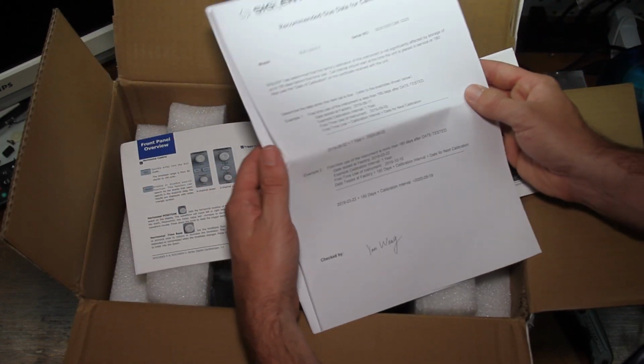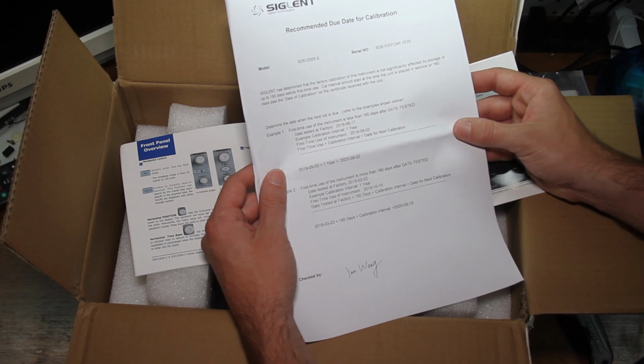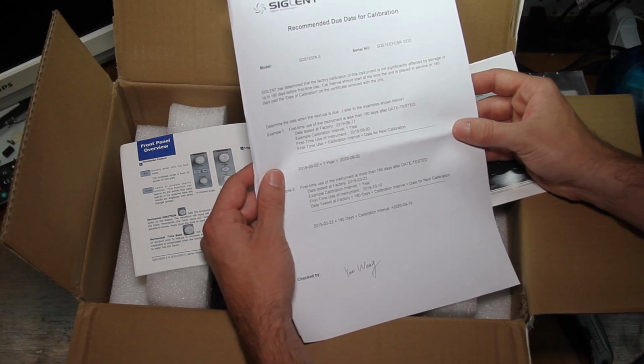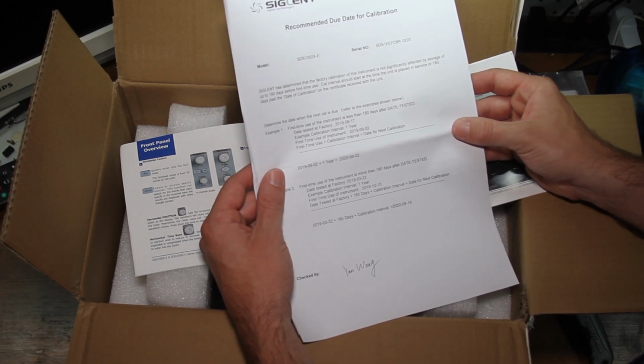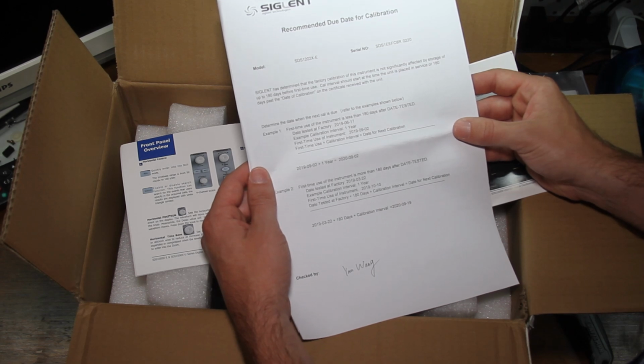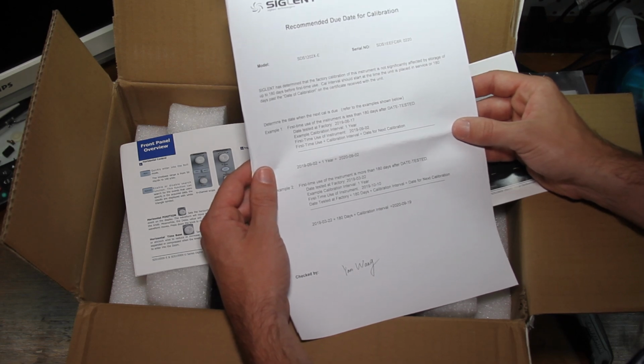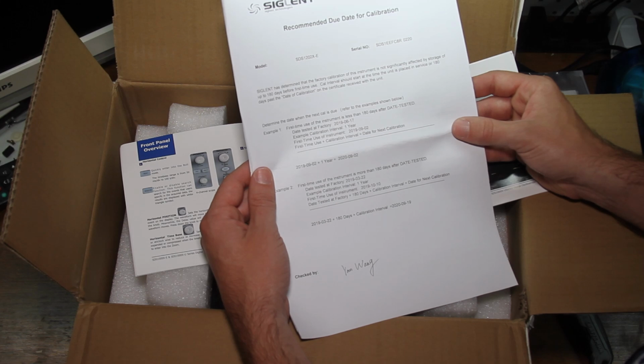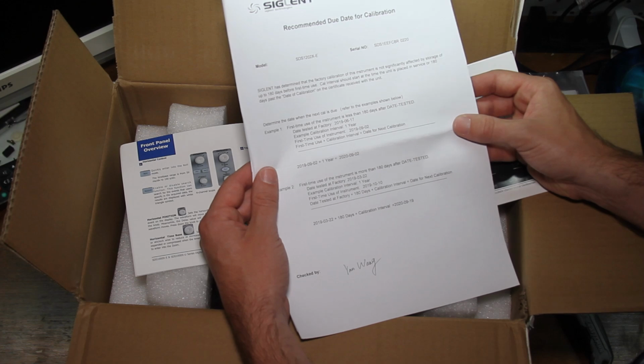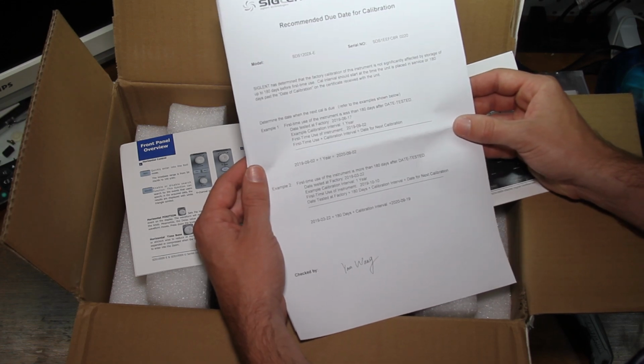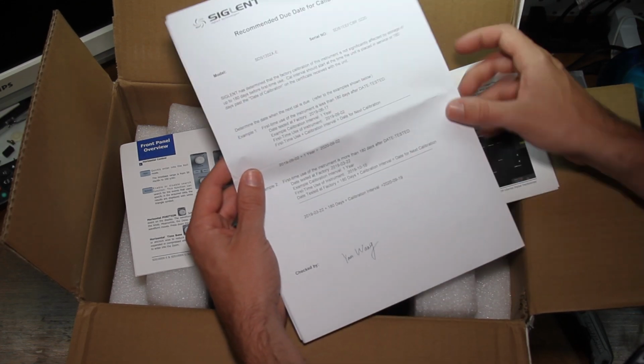Okay, so Siglent has determined that the calibration of this instrument is not significantly affected by storage of up to 180 days before first time use. Cal intervals should start at the time the unit is placed in service or 180 days past the date of calibration on the certificate received with the unit. Oh, this is just examples.